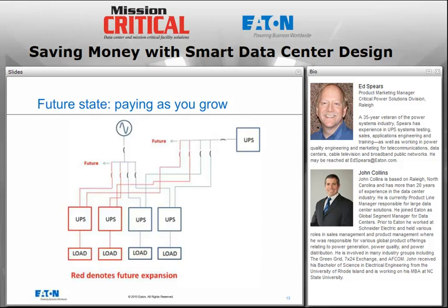In the smart catcher system, it's not required, but we can recommend that we go ahead and operate the catcher system in energy saver mode with its static switch already conducting. That does two things. It saves us on a lot of quiescent power to keep that catcher UPS running, and it means that when I suffer a fault on any of the primary UPSs, as soon as its static switch closes, I immediately have utility with its zillions of amps available to clear that downstream fault, whichever breaker or fuse is in series, and isolate that fault in the most expedient manner possible.